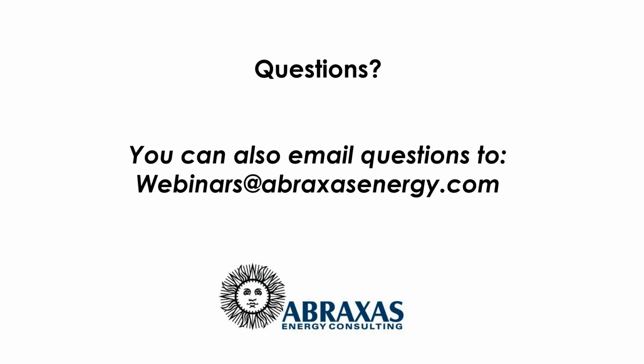Good. So it's time to answer questions, and I'm going to read one. It says, what parameters do you use to control the primary pump and secondary pump on variable primary, variable secondary systems? So it's basically on flow. If you can read your flow, and I've seen this more often with data centers where they have that exact arrangement where they have a bypass valve in the decoupler, they'll measure the flow on the chilled water plant and match that flow on the secondary loop, or vice versa, which is probably more accurate, is to maintain a differential between the two loops no matter what. So if you had 200 on the secondary, you want 250 on the primary. So it ensures that you're going to control the flow the right way.